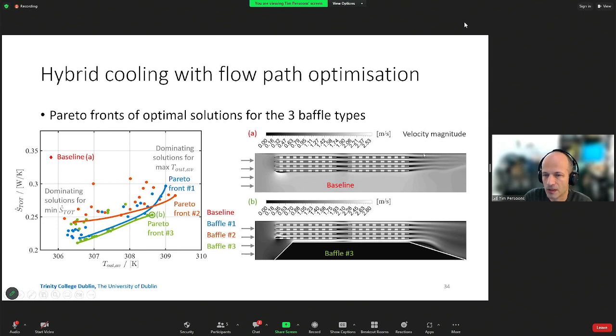And so from the baseline case, for instance, you're looking at the velocity magnitude here on the right. If you introduce a baffle, that means that you're channeling more flow through the DIMMs, which is what we want to do. And what it also means is that you're able to reduce the velocity magnitude, right? If you look at the typical velocity magnitude initially in the baseline case, it's maybe something like 2 meters per second. You're able to reduce that quite a bit to something like 1 meter per second, maybe, because now you're cooling these DIMM modules much more effectively. And of course, we also want to look at the shape of the baffle downstream, because we want to pull open the flow over here and make sure that we have a uniform distribution of flow that goes over the heat exchanger at the rear of the server.